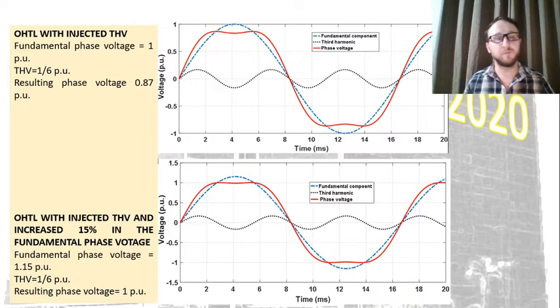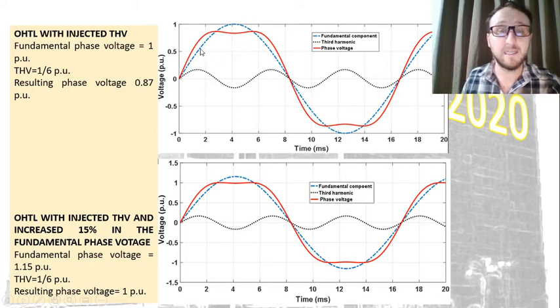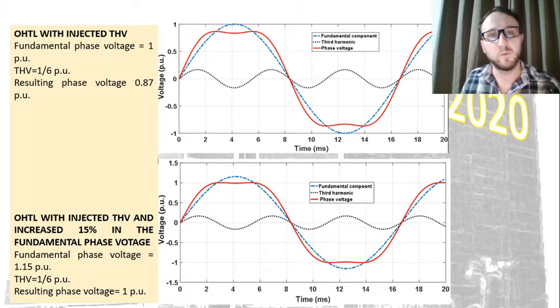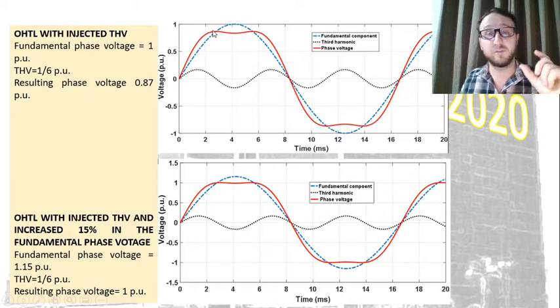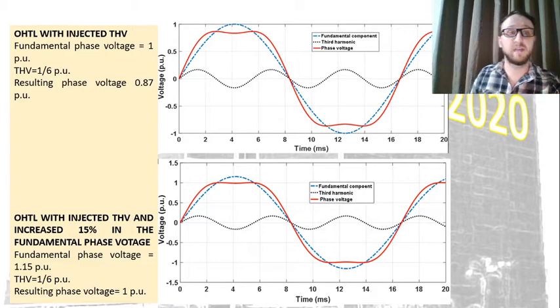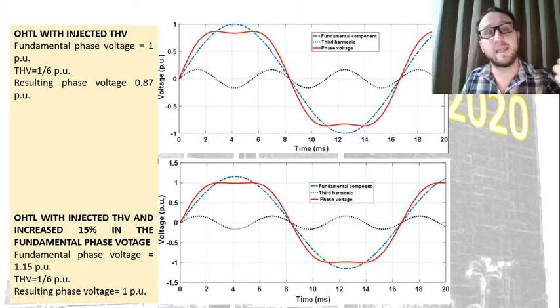How does it work? When we have a fundamental wave at 60 Hertz, we have this waveform here, and once we apply a third harmonic voltage and add one curve to the other, we have a reduction at the peak of this waveform, and this is done at the phase voltage, because we don't change the line to line voltage, it remains the same.